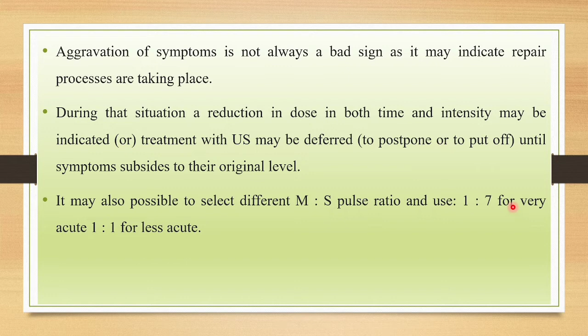It may also be possible to select different mark-space pulse ratios, using 1:7 for very acute and 1:1 for less acute. And dosage in chronic conditions. Chronic conditions may be treated with pulsed or continuous mode. The maximum intensity of ultrasound which should be used is that which produces mild perceptible warmth. This usually occurs around 2 watts per centimeter square.